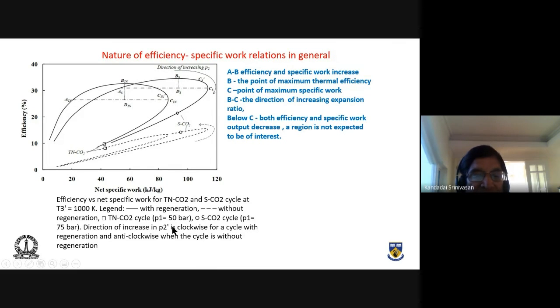I am plotting this for a transcritical cycle where the starting low side pressure is 50 bar. For the supercritical cycle, the low side pressure has to be 75 bar, which is pretty close to the critical pressure; it has to be above the critical limit. This is in the direction of increasing pressure. As you keep increasing, beyond this particular point you don't get anything.